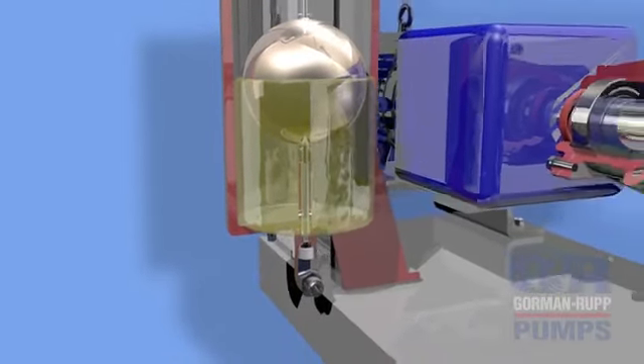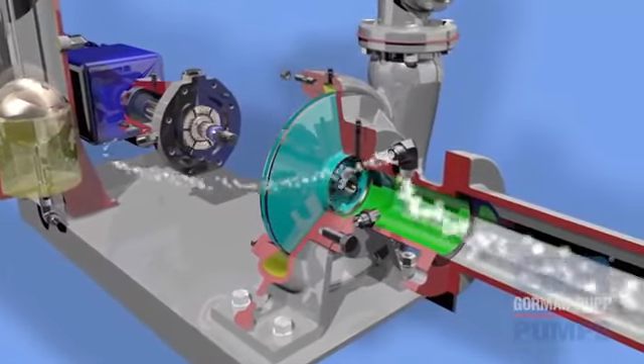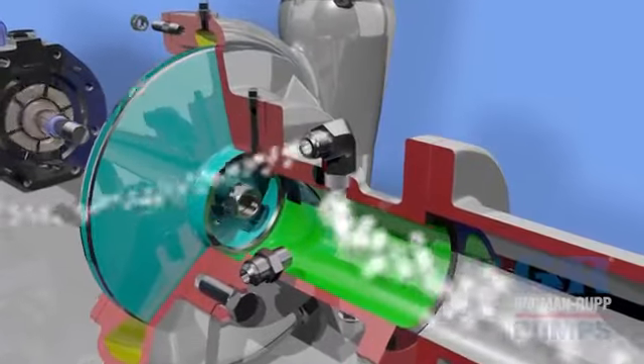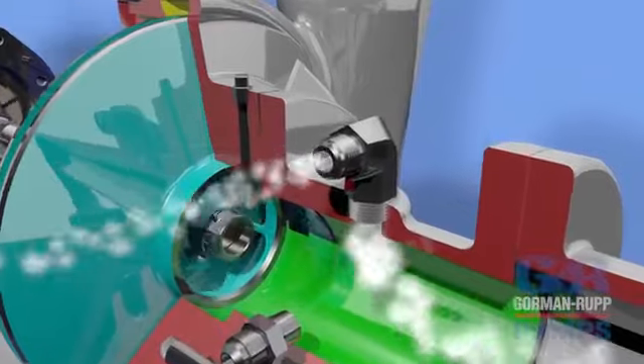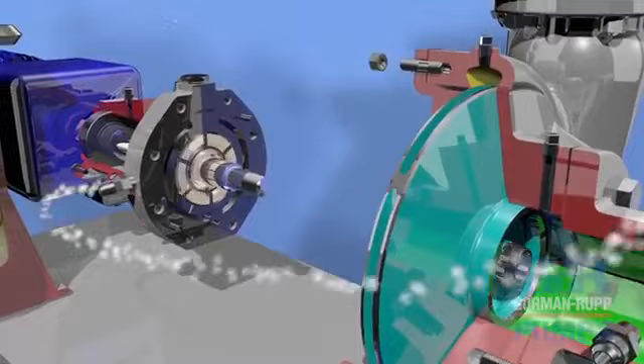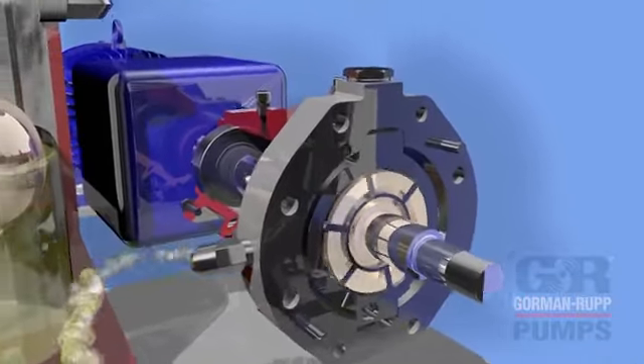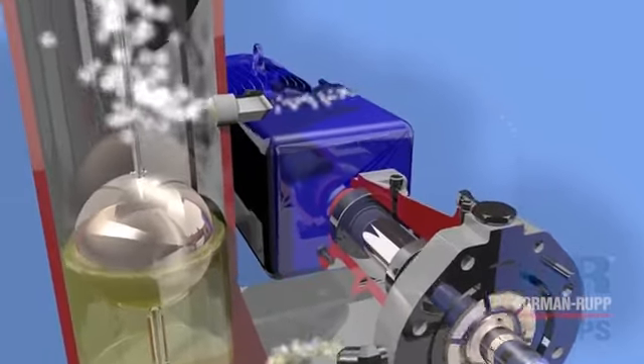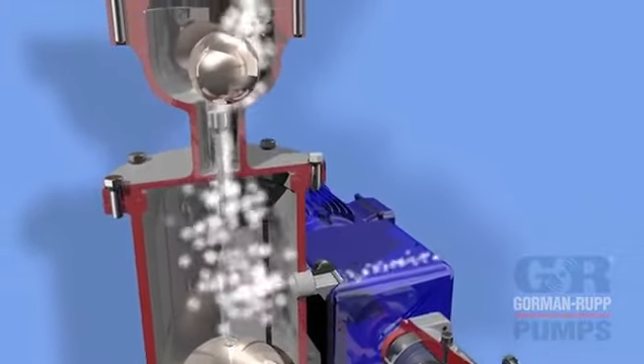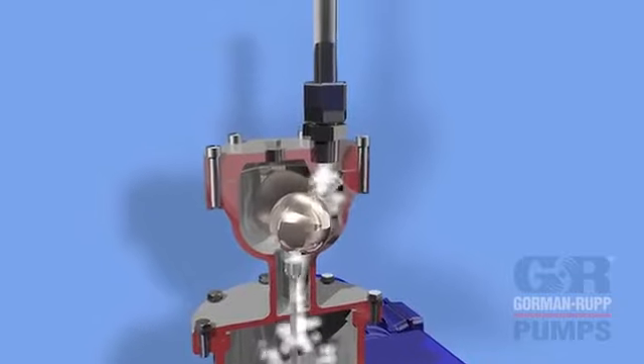The pump operation remains the same during the priming sequence, with the exception of air and vapor being routed to the priming pump from a priming tube on the suction inlet. For enhanced priming characteristics, priming through the impeller and body cover are not utilized in any BAR models. A discharge tube from the priming pump is routed to the air release valve, which allows air and vapor to be exhausted. This valve should be routed to a collection tank.